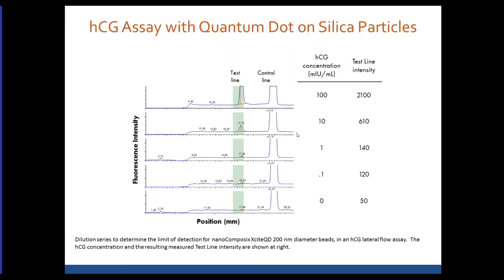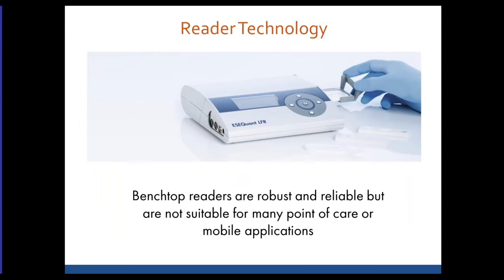On our reader, a scan of fluorescence as a function of position shows a bright control line and test lines whose intensity we quantify by integrating under the curve. At relatively high HCG concentrations you get a large signal, and as you go lower the signal diminishes. We're getting down to about 0.1 mIU/mL for HCG, which is roughly an order of magnitude better than the best pregnancy tests on the market today. These particles are providing a very sensitive readout for this particular assay.